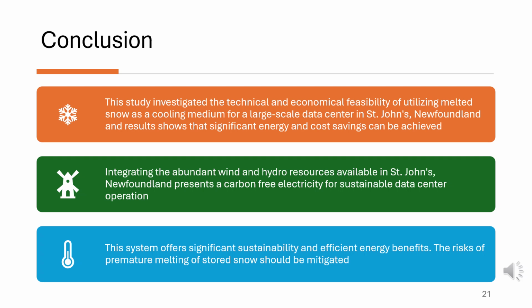Just a little recap. This project explored the technical and economic feasibility of using melted snow and the winter air as a cooling medium for a data center here in St. John's. And the results are quite revealing because a traditional chilled water system uses nearly 25,000 megawatt hour per year, while this system only uses about 3,300 megawatt hour per year. That is so different, right? So not only does this system save energy, it saves money, and it reduces the demand on the city's water, whatever location. It reduces the demand on the water infrastructure there already. And also, by integrating the abundant wind and hydro resources available here in St. John's, we can also reduce the demand on the electricity grid by using the system.